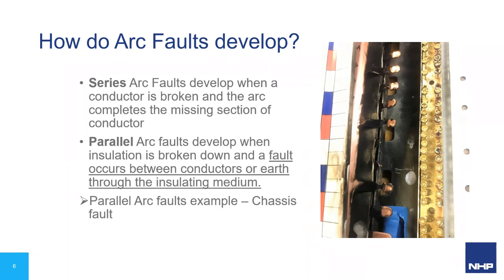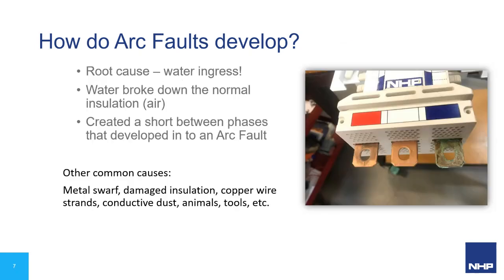So we've got a bit of a better photo here showing what can happen. You can actually see between those tags, we've got material being chewed away, and there are two tags there completely missing. So this is an arc fault that's extended for an extensive period of time. It's always interesting to see how these things come up. With this one, it was a fairly straightforward investigation.